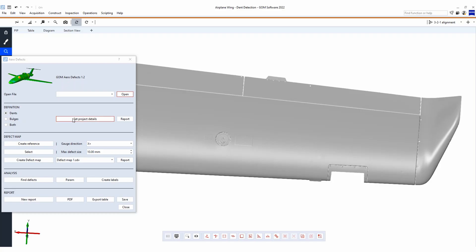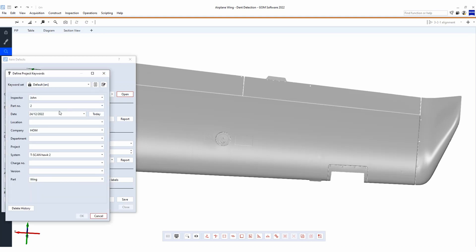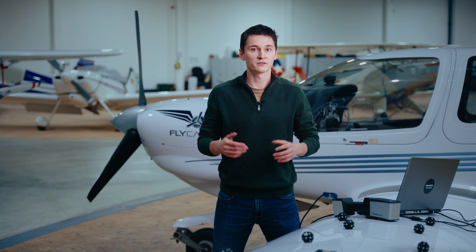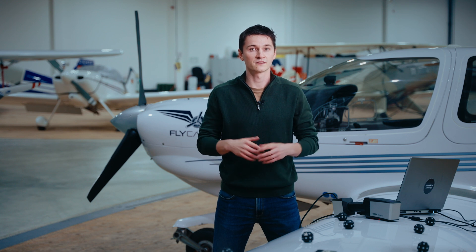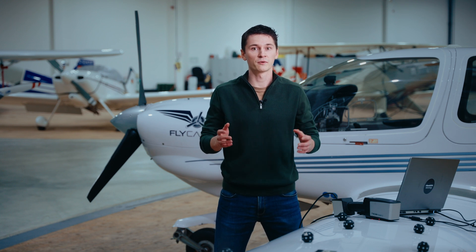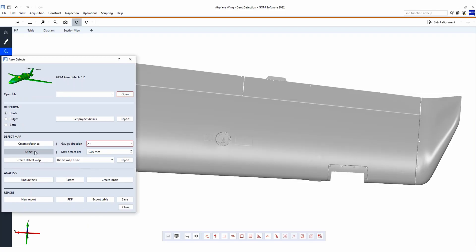If we open our aero defect package, we can set up our project parameters and references. These can be used for reporting to visualize the area for operators and technicians who need to repair the defect. By selecting the area and the maximum defect size, the software shows the defect map.